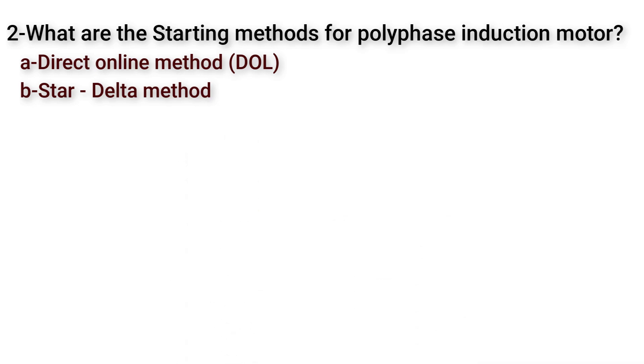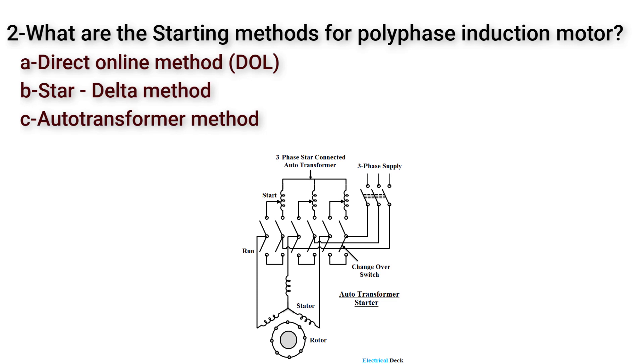The third method is auto transformer. This is an old method. We use here a single winding transformer which acts as primary and secondary winding at the same time. Here the auto transformer reduces the voltage applied on the motor at starting. Then the auto transformer will be disconnected when the motor reaches its rated speed.